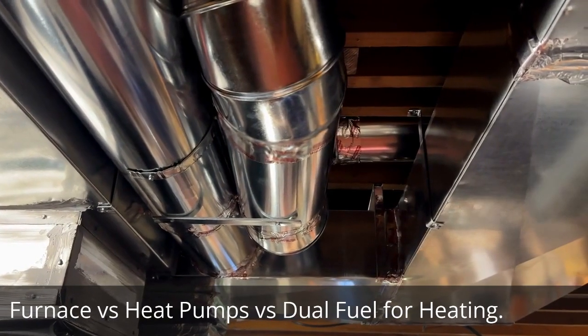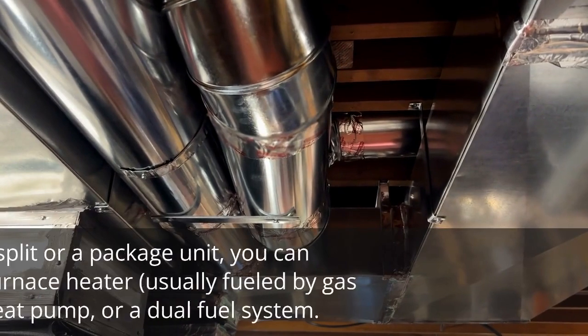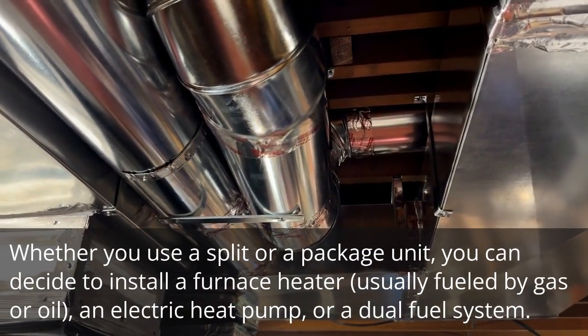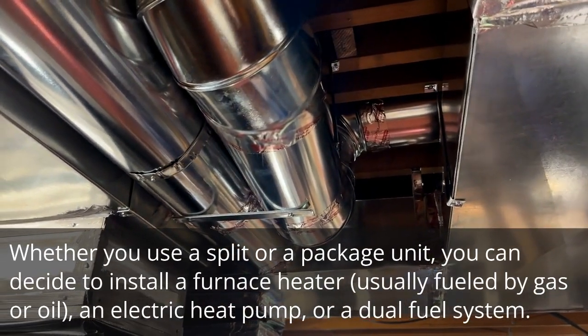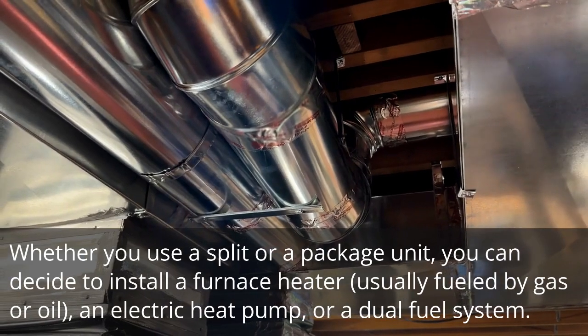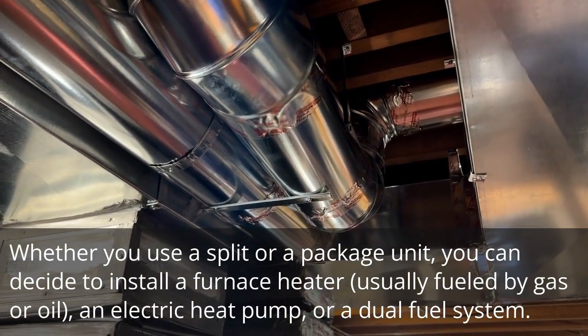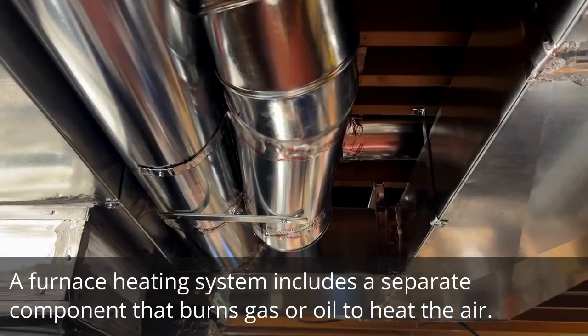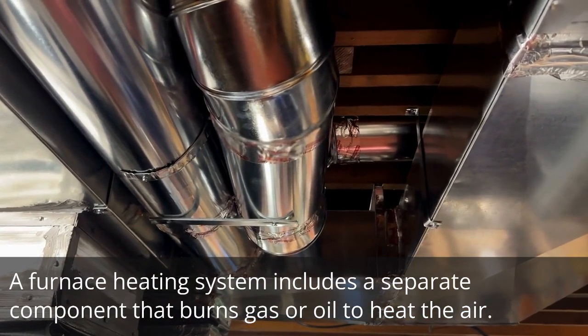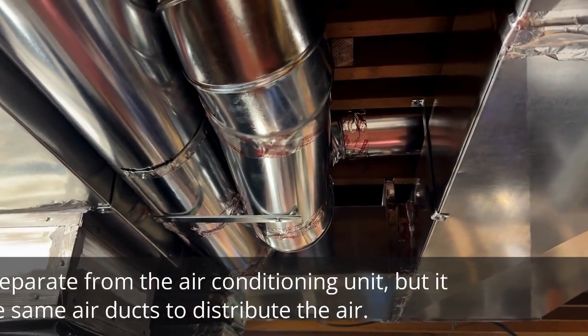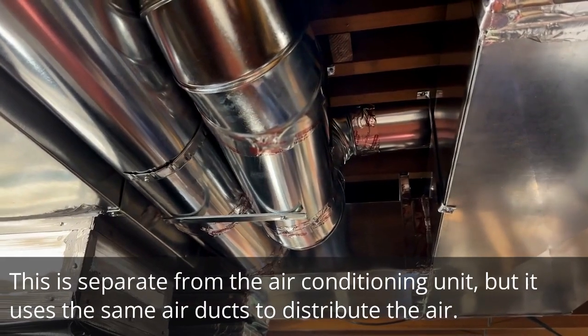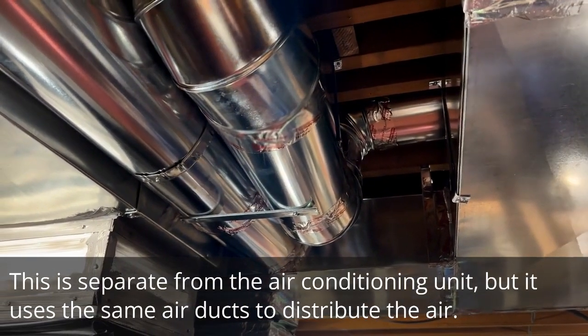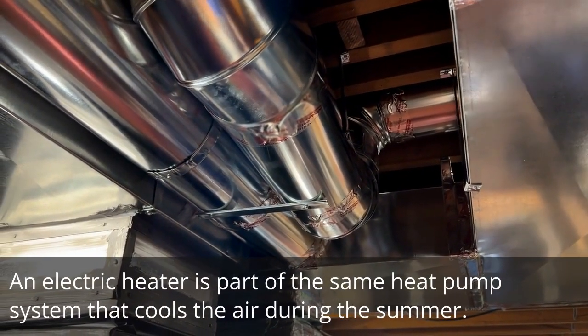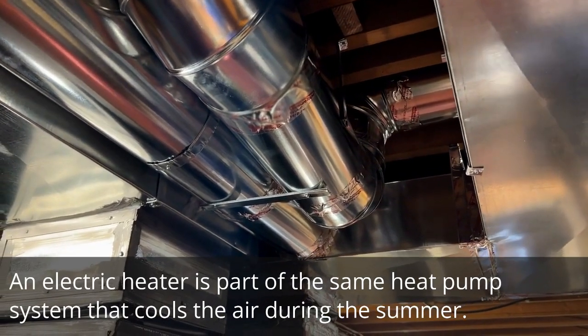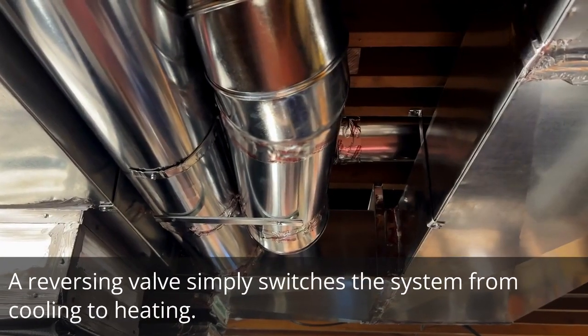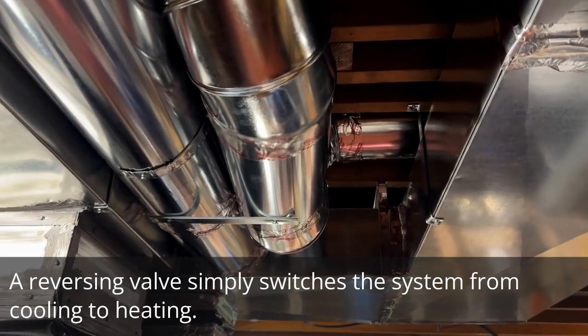Furnace versus heat pumps versus dual fuel for heating. Whether you use a split or a package unit, you can decide to install a furnace heater, usually fueled by gas or oil, an electric heat pump, or a dual fuel system. A furnace heating system includes a separate component that burns gas or oil to heat the air. This is separate from the air conditioning unit, but it uses the same air ducts to distribute the air. An electric heater is part of the same heat pump system that cools the air during the summer. A reversing valve simply switches the system from cooling to heating.